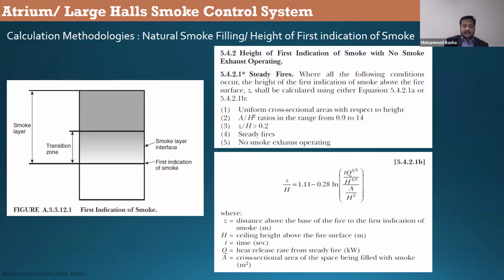So basically, if you are using this system, as I have explained before, there is no need for a smoke exhaust system, but we need to ensure that the occupants can evacuate before the smoke comes down. How to calculate this? That is this formula. There are some restrictions for using this formula or this system. The major restriction is the ceiling should be flat. The ceiling cannot be in an irregular shape or a sloped condition. It should be a flat ceiling.